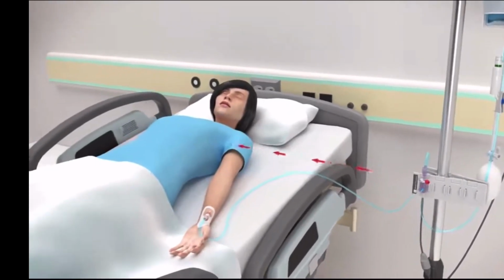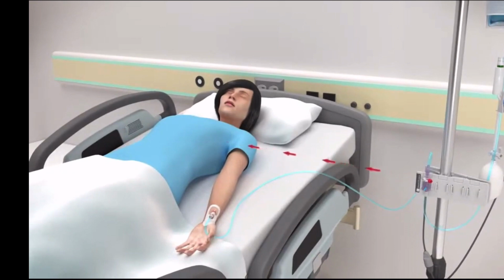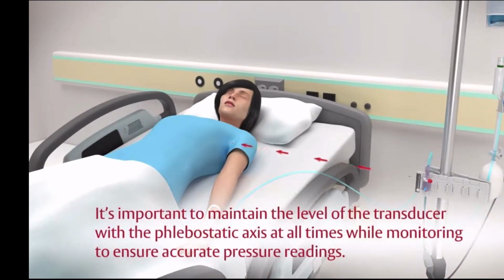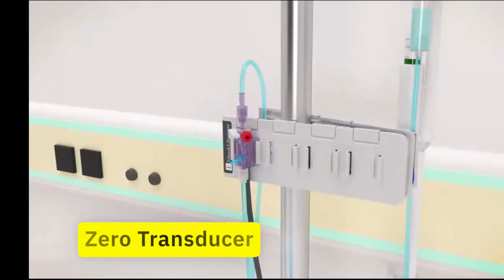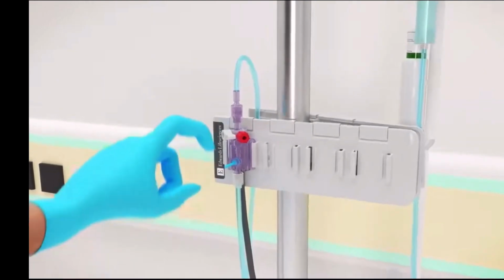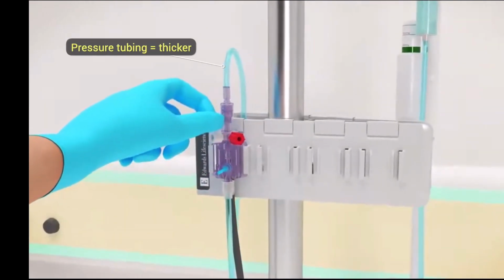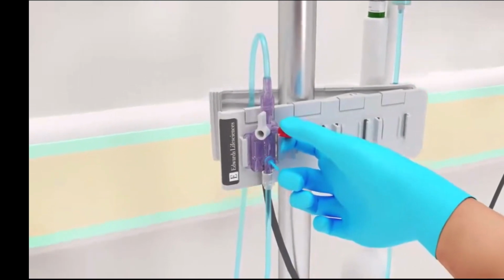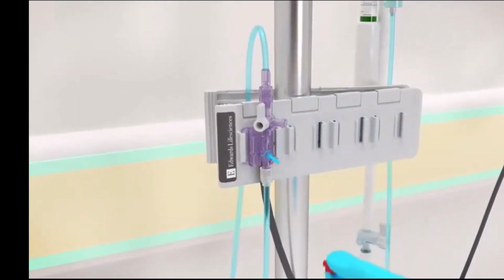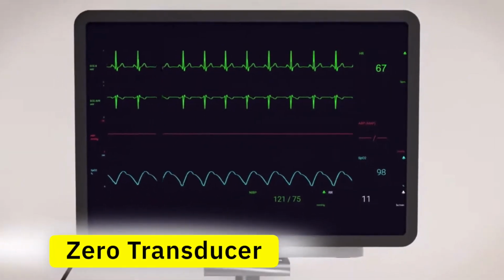For intravascular monitoring, level the transducer to the patient's phlebostatic axis, which is found at the midpoint of anterior and posterior chest wall at 4th intercostal space. It's important to maintain the level of the transducer with the phlebostatic axis at all times while monitoring to ensure accurate pressure readings. Zero the transducer to remove effects of atmospheric pressure. Open the stopcock above the transducer to atmospheric air by turning the stopcock towards the patient's pressure tubing and away from the TrueWave transducer.